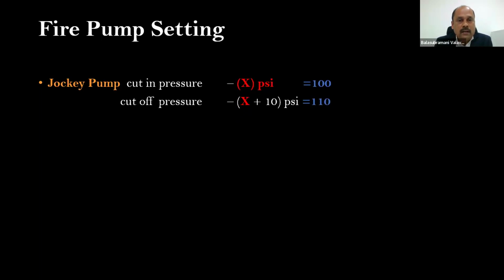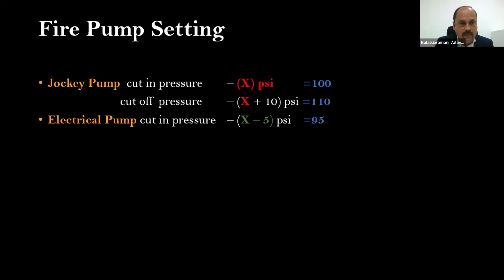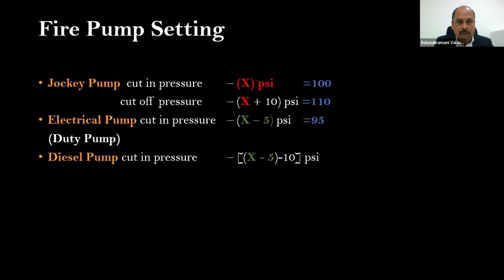For some reason, if the sprinklers are broken because of the actual fire, it will try to maintain the pressure. If it doesn't manage, the electric pump will come into the picture, at x minus 5, 95 psi. Then the electric pump will run. It allows the water to spray on the actual hazardous area where the fire is happening. Suppose there is a problem in the electric pump for whatever reason, immediately the diesel pump will come into the picture. There will be a further reduction of pressure, which is the standby diesel pump.